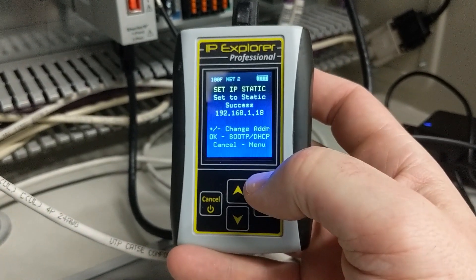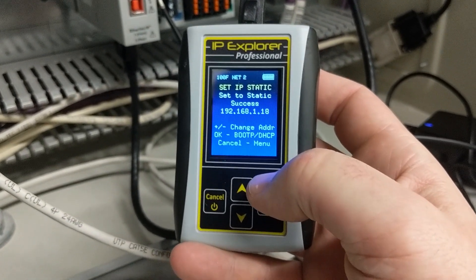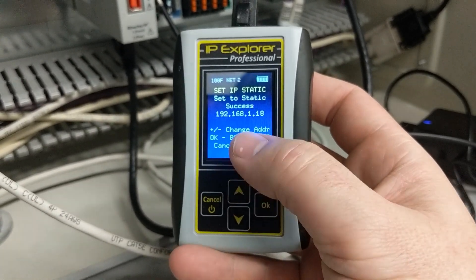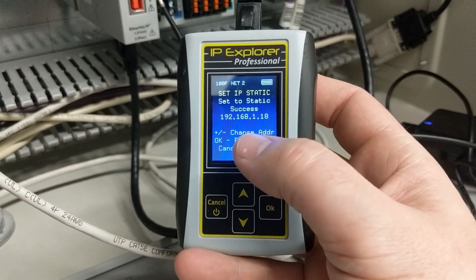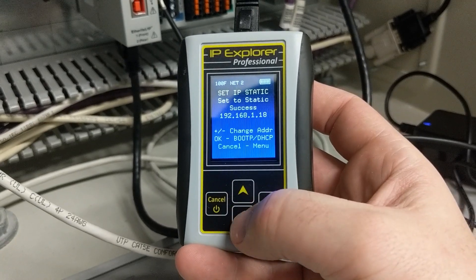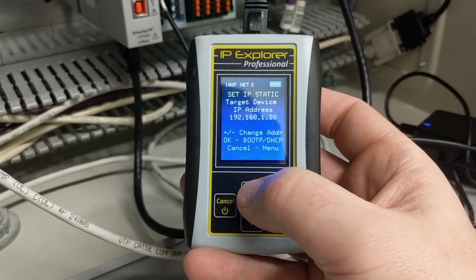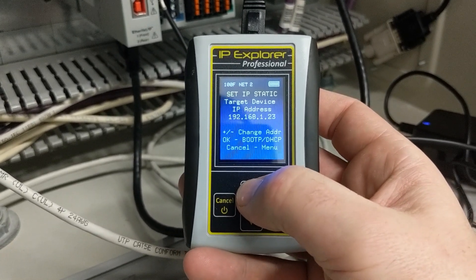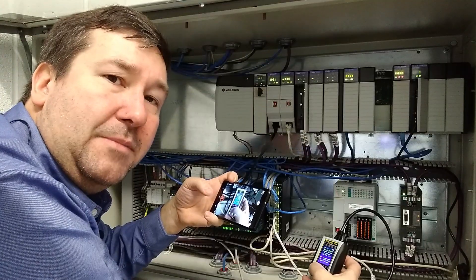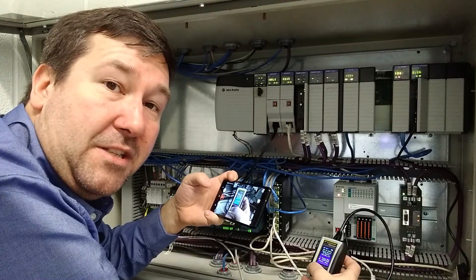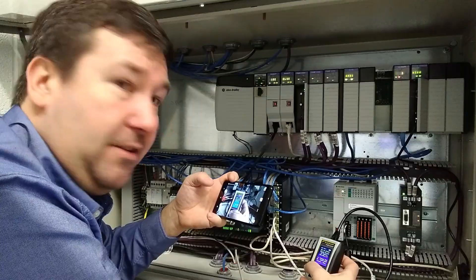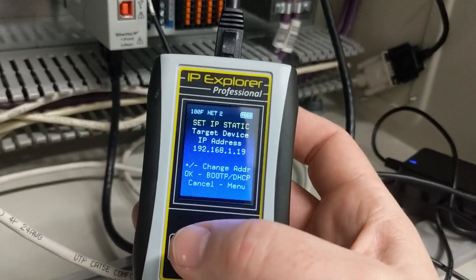Now here's a neat feature for people who are commissioning systems: right now it says change address plus minus. You can use the up and down arrows to change to the next IP address. Many times when you're commissioning a system, the IP addresses are incremental. So this was 18, your next one will be 19.